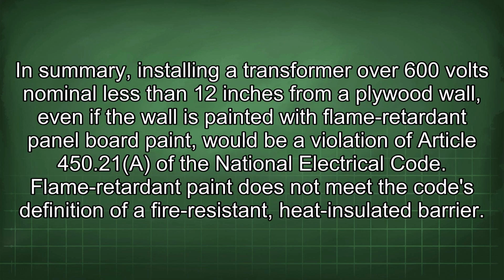In summary, installing a transformer over 600 volts nominal less than 12 inches from a plywood wall, even if the wall is painted with flame-retardant panel board paint, would be a violation of Article 450.21 of the National Electrical Code. Flame-retardant paint does not meet the code's definition of a fire-resistant heat-insulated barrier.